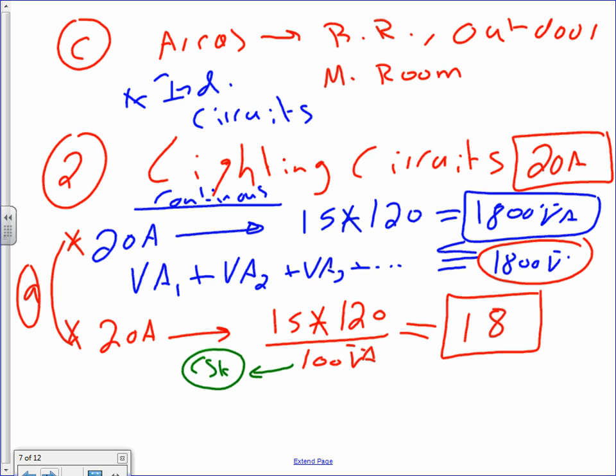Now, outdoor area. This is what I call it. Again, these are my opinion, and a lot of people agree with that. I call these areas, guys, for receptacles. Areas like bathroom, outdoor, machine room, individual circuits. That's my opinion. For example, I have 3 receptacles on the outside of the building for outdoor. It's a very good idea to give them a dedicated circuit, not sharing with others. Design, remember, design. Code-wise, I can still do the 18.